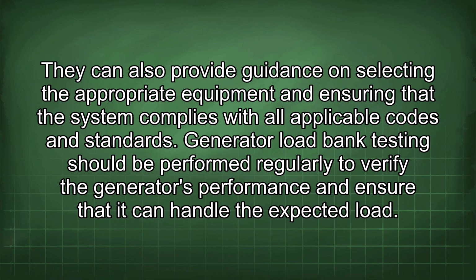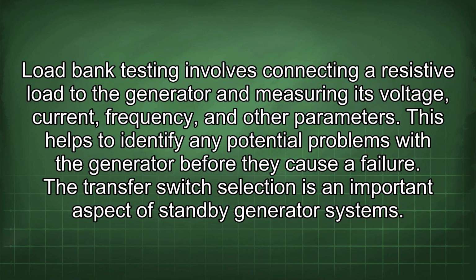Generator load bank testing should be performed regularly to verify the generator's performance and ensure that it can handle the expected load. Load bank testing involves connecting a resistive load to the generator and measuring its voltage, current, frequency, and other parameters. This helps to identify any potential problems with the generator before they cause a failure.